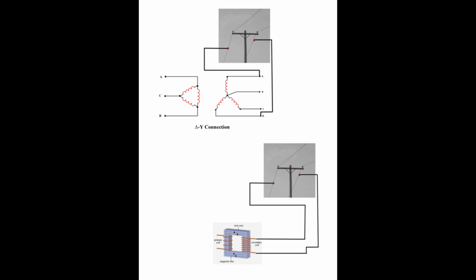To emphasize the advantage of three-phase over single-phase, the two connections shown of two-wire medium voltage distribution line are connected to two different sources. The first line is connected to a three-phase Y-connected source, on lines A and B respectively. The second line is connected to a single-phase source, to which only a single-phase transformer can be connected. The first configuration, although with only two wires, makes it possible to install a three-phase system using two single-phase transformers connected in open delta. The capacity rating of this network is 57.7% of the closed delta equivalent of the transformers.